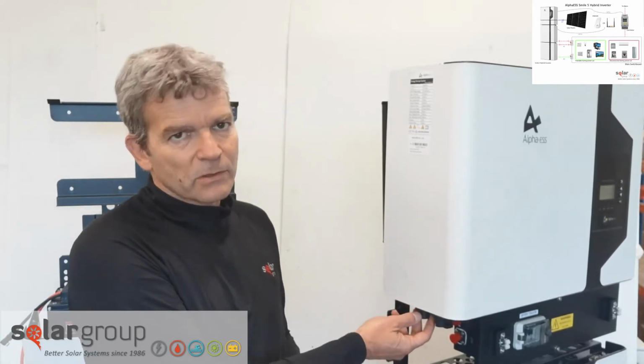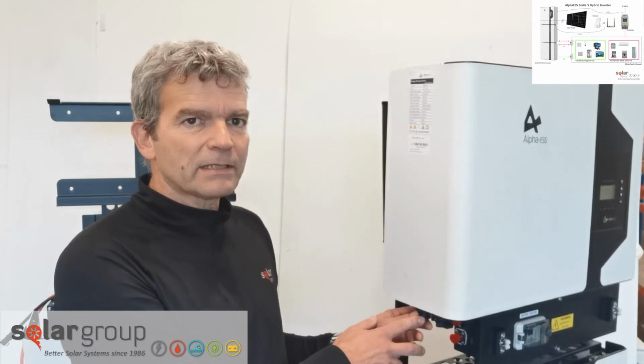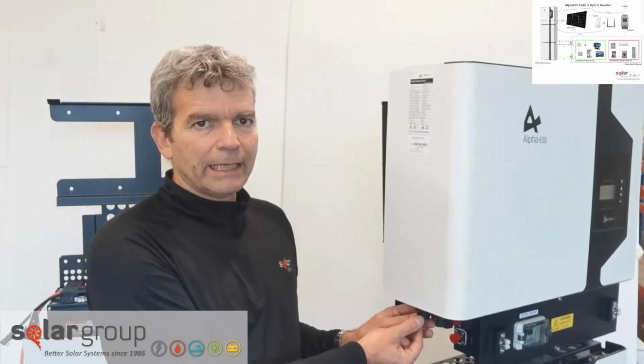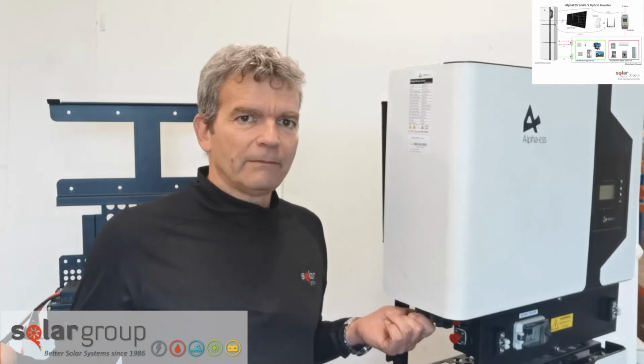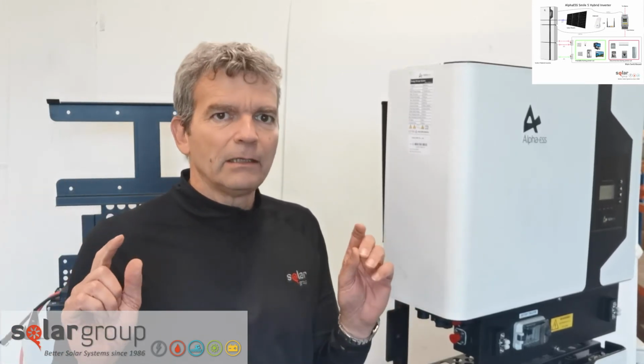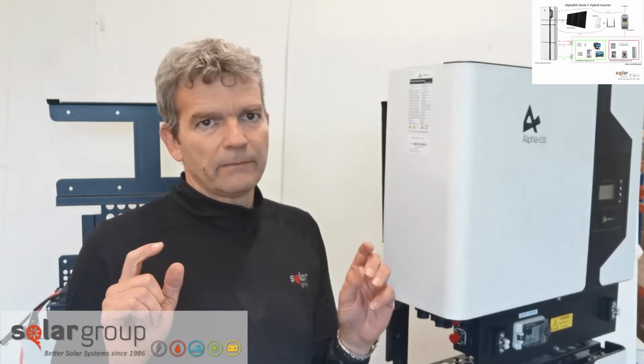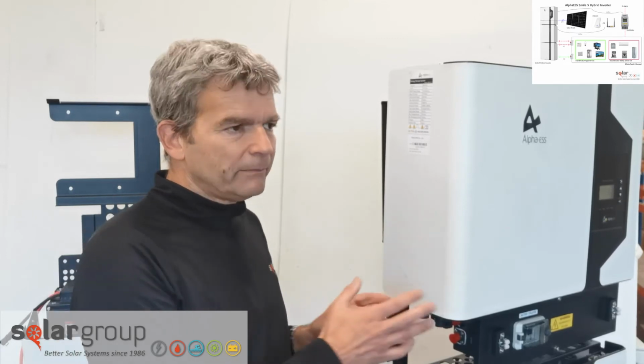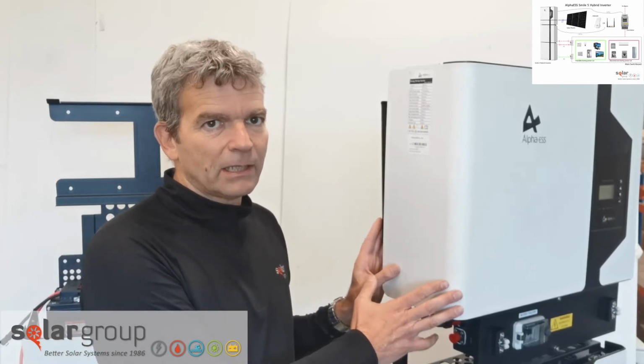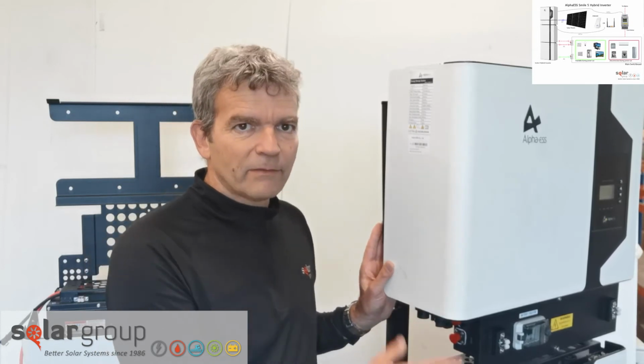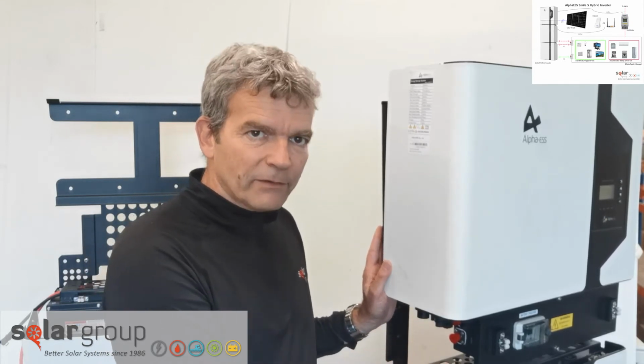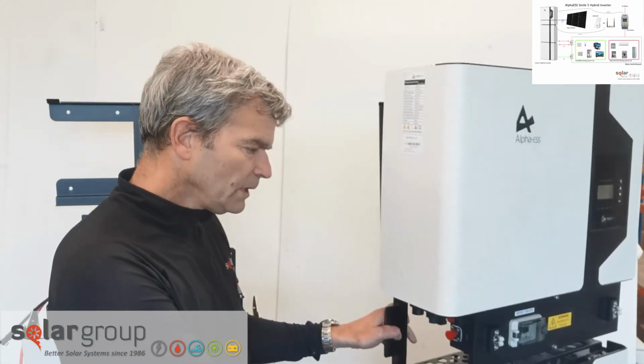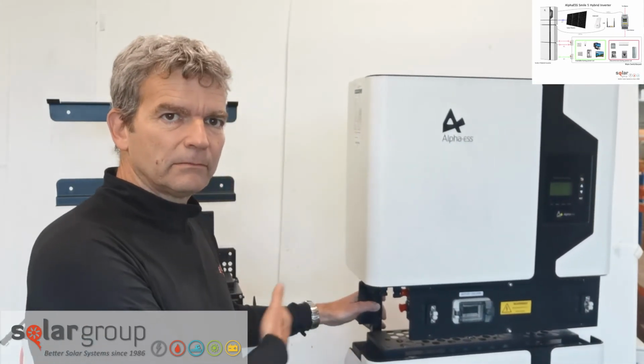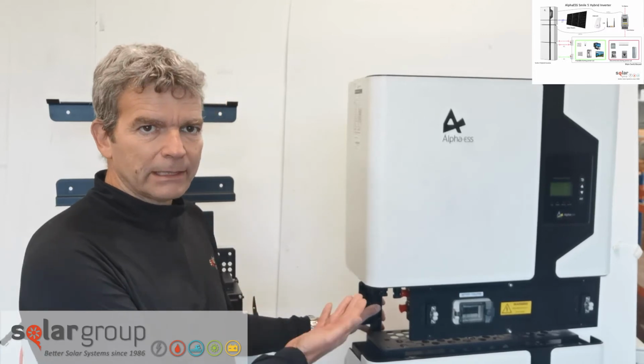If you don't have backup, you don't have to do the backup. Most commonly people will have a backup, so as we discussed with the B3, from here, again, a 4mm lead, 25 amp circuit breaker to the dedicated DIN rail of the backup. Same as the B3, you can look at the webinar there. So lighting and etc. etc. The limitation of the backup is 5 kilowatt, and if you have only one battery, as Fletcher mentioned before, it's going to be 2.5 kilowatt limitation. So we have the battery cable and the AC.